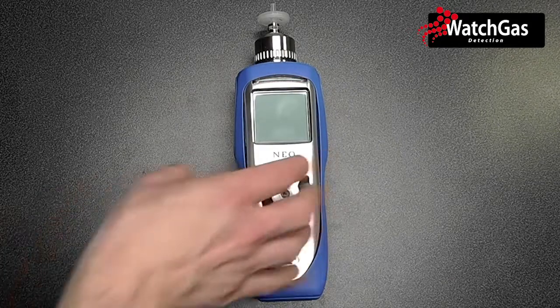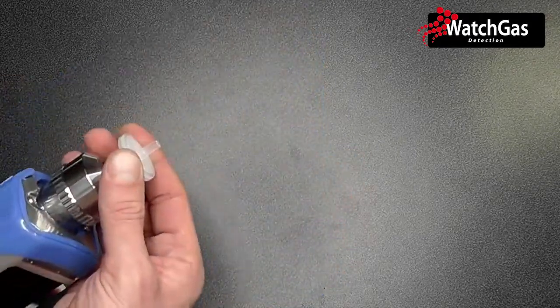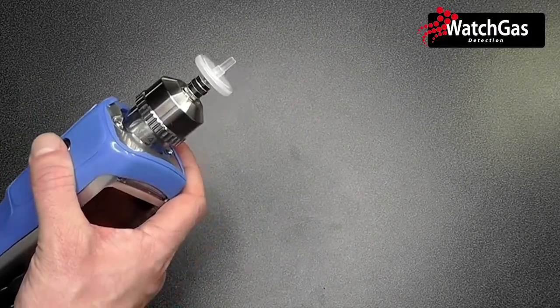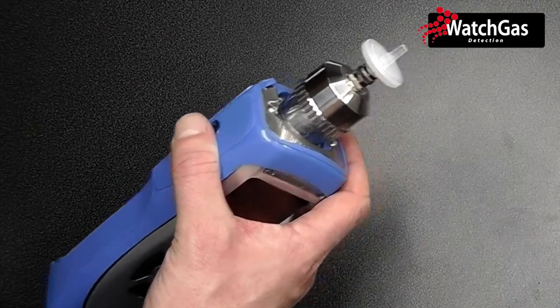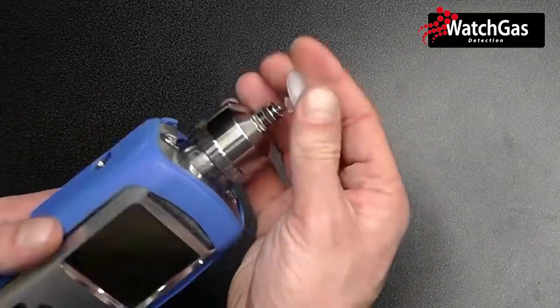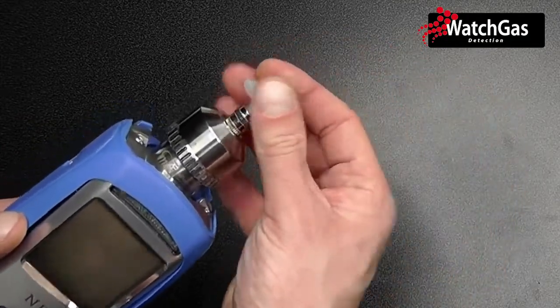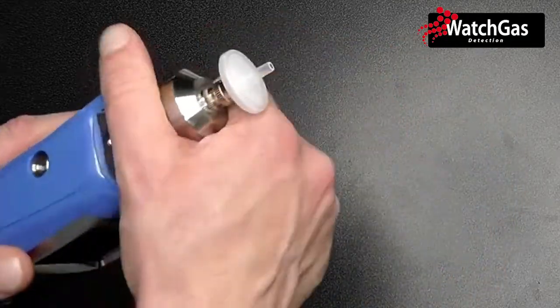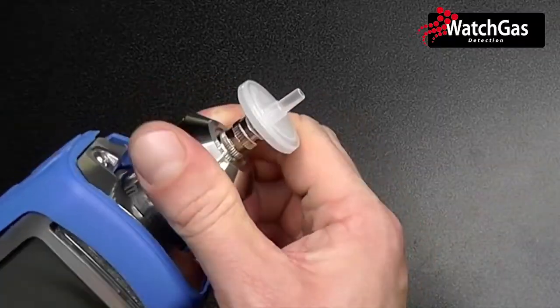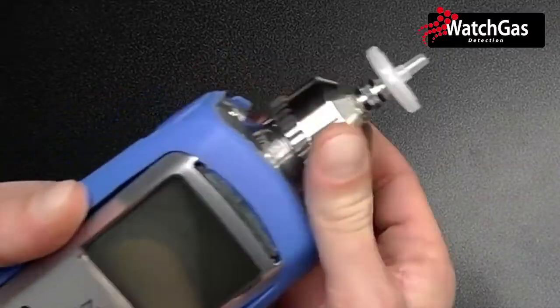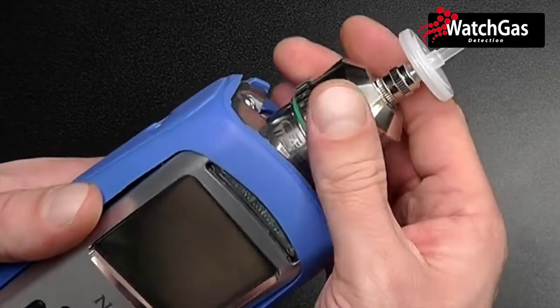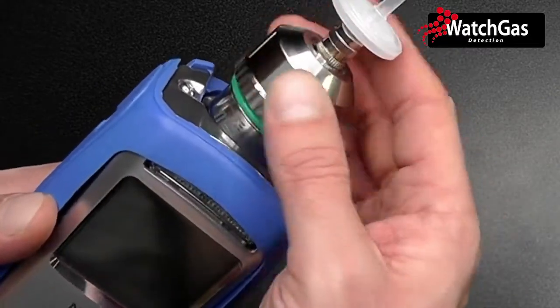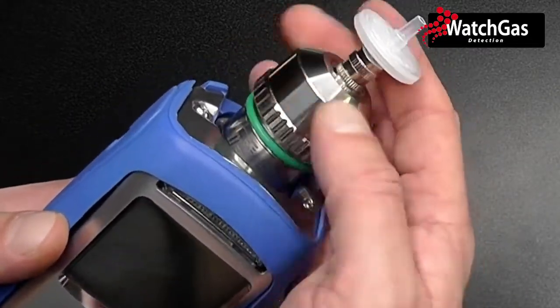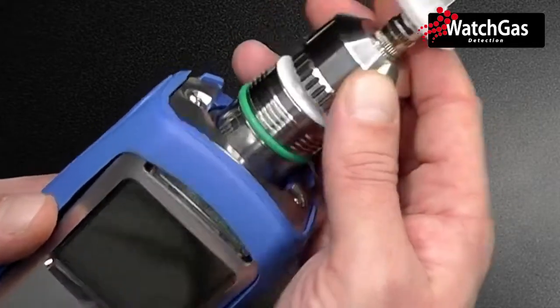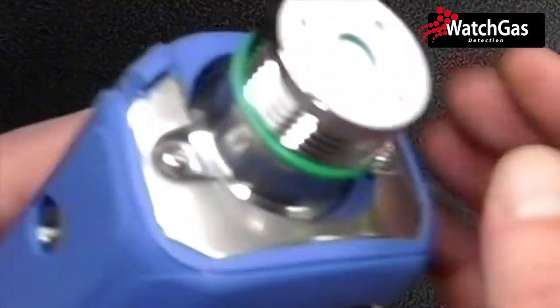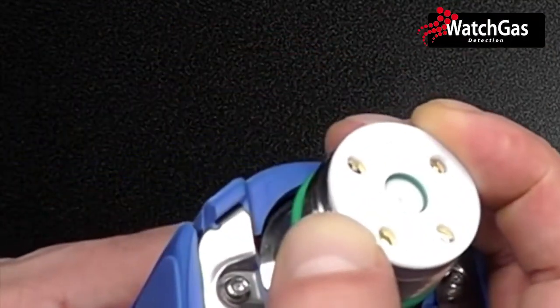Now if we want to look in any more detail at the external, we can see we have an external filter fitted as standard on the device. The unit comes with about 5 or 6 in the box. These are easily removable, replaceable and reattachable. And then if we want to get into our sensor section, up the top, we unscrew the top section here, and we can see that our PID is positioned right at the front end of the device. So the PID lamp sensor is here, and then underneath is our actual lamp itself.